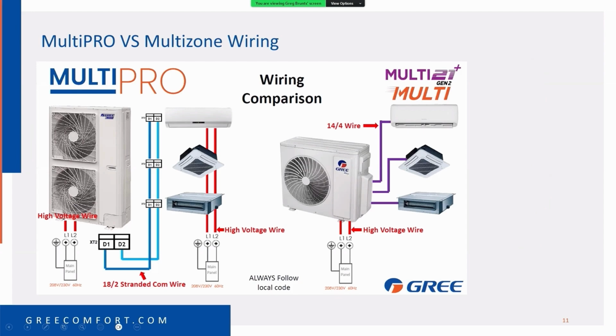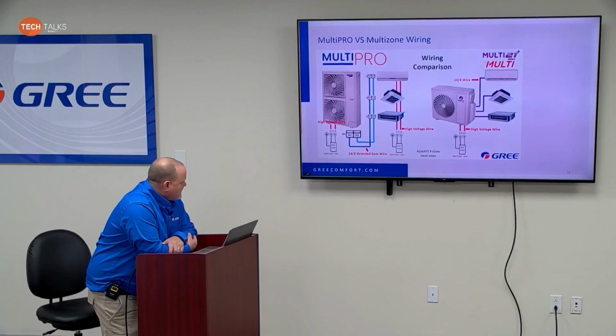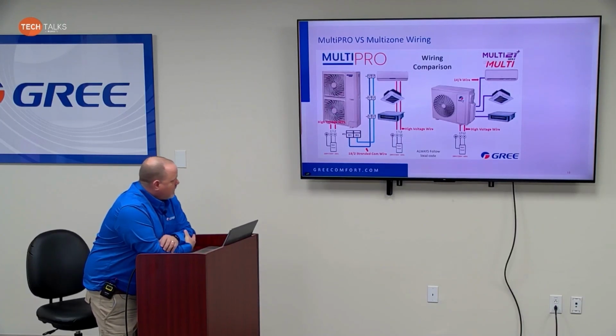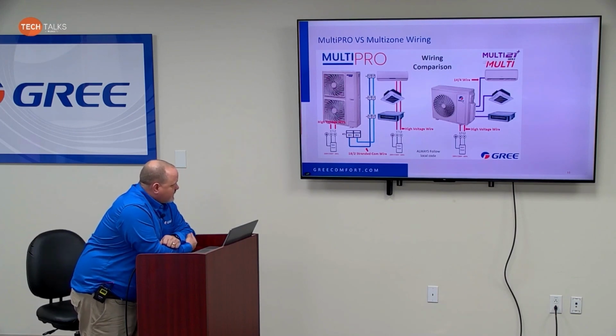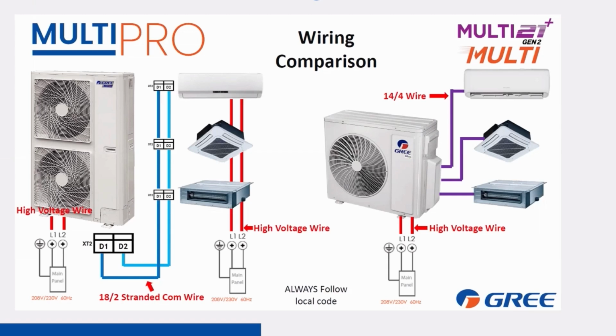Part of the reason I decided to cover installation again is that I don't think the message has gotten out to everybody who is now being introduced to and installing MultiPRO. This is a good example of showing you how MultiPRO differs from mini-split multi-zone in the wiring. On a mini-split multi-zone unit such as you see here, you have individual line sets for each indoor unit and the 14-4 wire that will power the indoor units. So your 14-4 wire is also your communication and power supply to your indoor units.